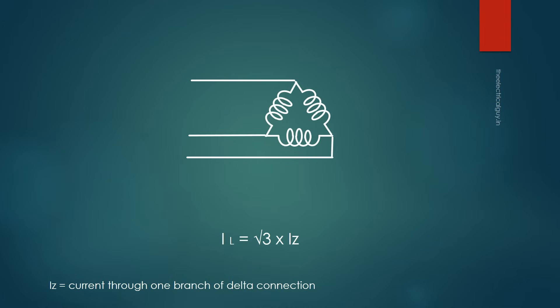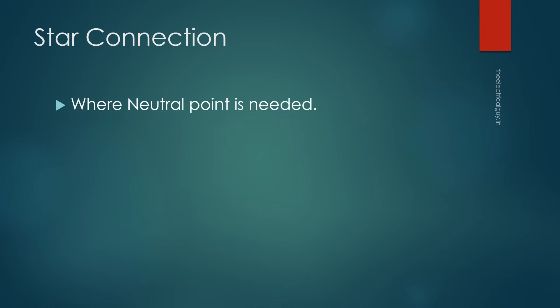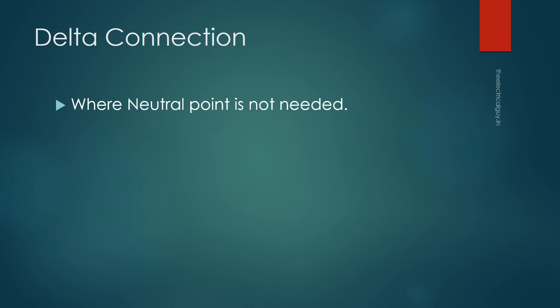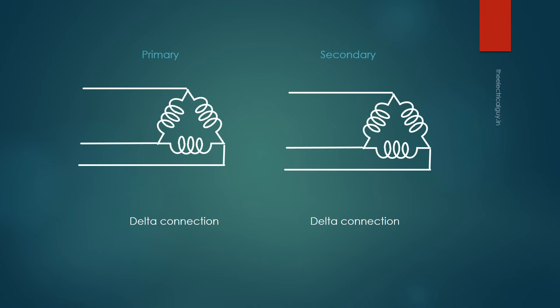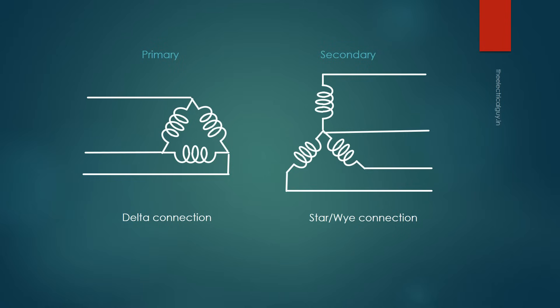Generally, star connection is used where a neutral and two separate voltages are needed, such as in distribution systems. Delta connection is preferred where a neutral conductor is not needed, such as in high-voltage power transmission, and also where third harmonics need to be controlled. You will find three-phase transformers connected in different combinations: star-star for auto-transformers, delta-delta for high-voltage transmission, and delta-star as distribution transformers.